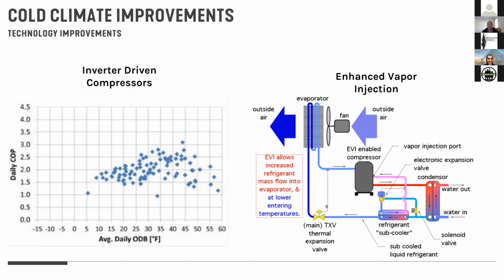And you can see that even with an inverter-driven compressor, it still is not hovering at 3. What everybody's using for their carbon intensity conversions, oh, it's a COP of 3, it's great, every hour of the day is wonderful. That's not true. And so the COP is dropping off, but inverter controls will allow you to at least bump that back up and hold it relatively steady down until you get to the 0 degree Fahrenheit mark. After that, it's pretty much an electric resistance heater.